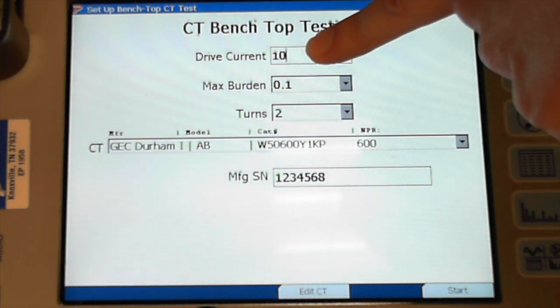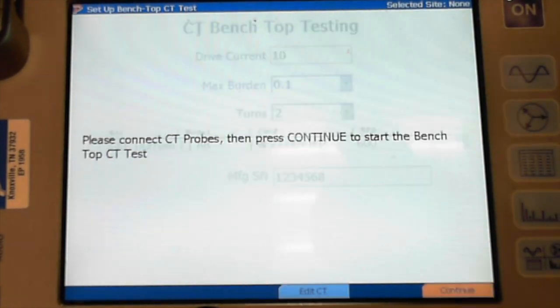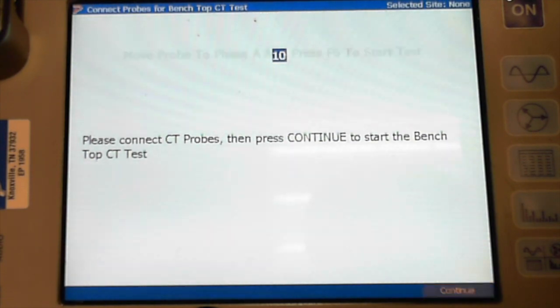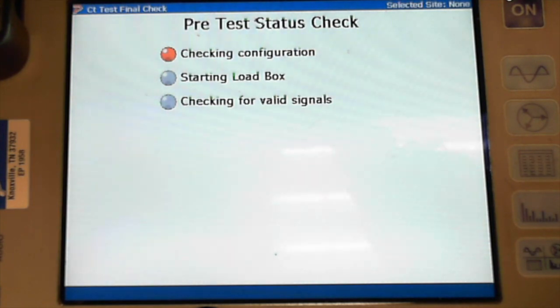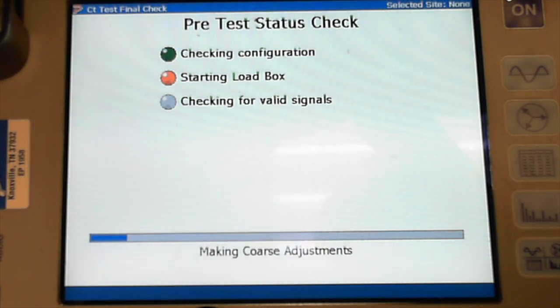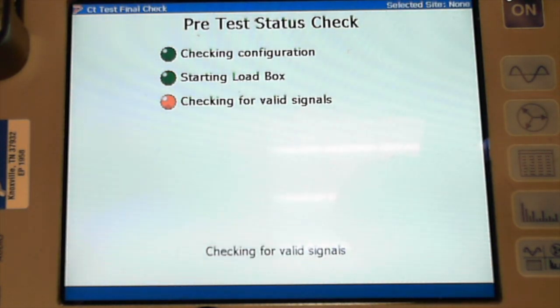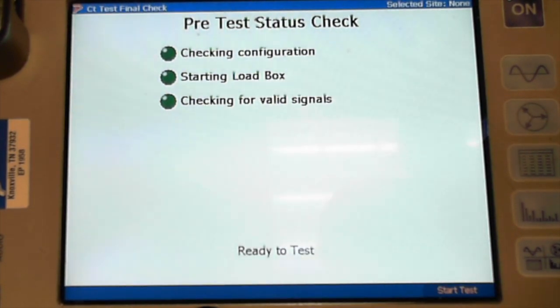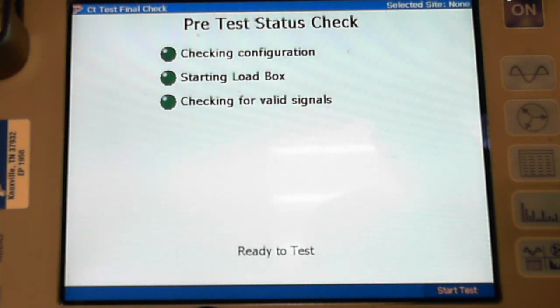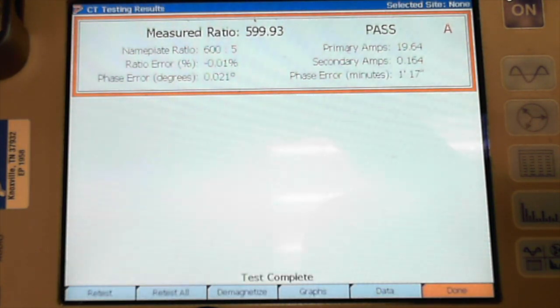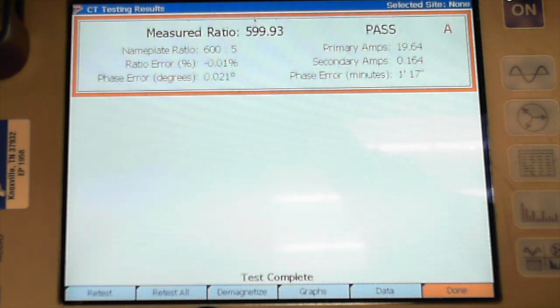And that'd be 20 amps going down there. So I'm below the 5% range now, right? So when we hit start, it's stabilized to make sure we get exactly 20 amps going to that transformer. Ready to test. 0.01% at below its manufacturer spec. So Nick, you've got a fantastic CT here. That's all I've got to say. So I'll turn it back over to Nick now.